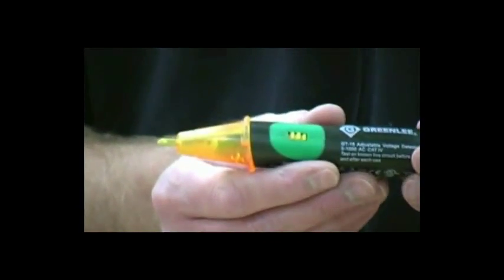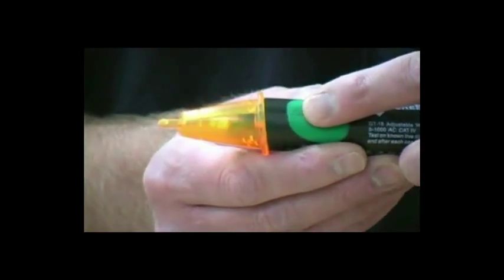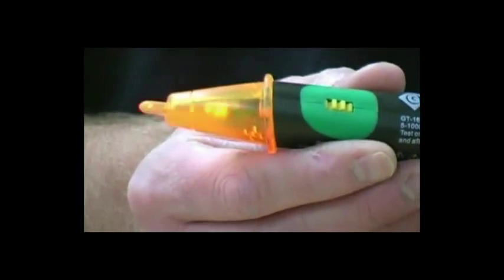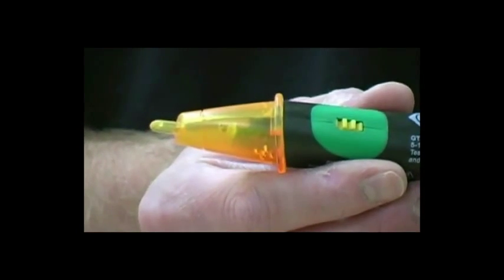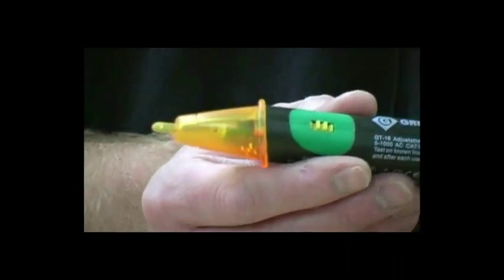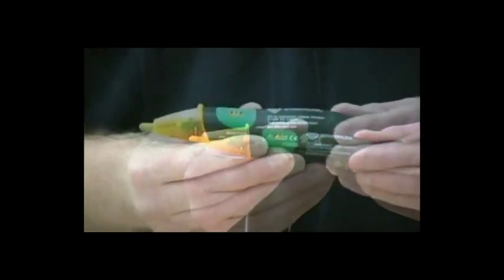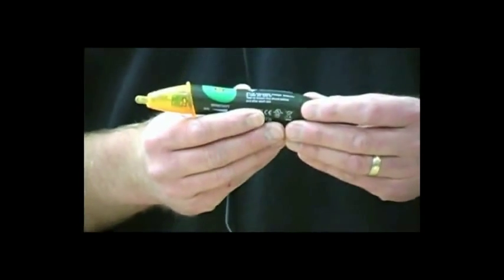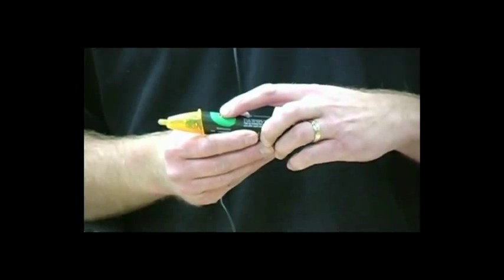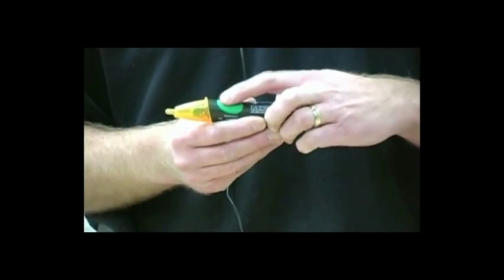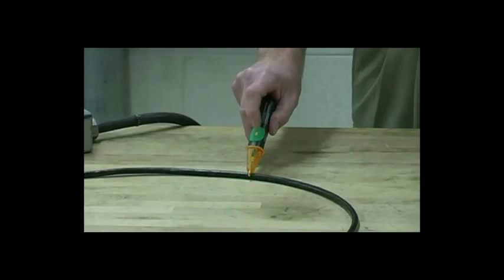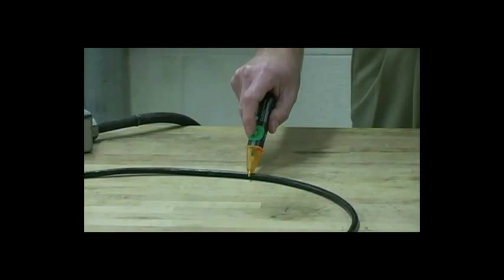To turn on the GT16, rotate the thumb wheel toward the tip. Verify the LED is blinking about every 2 seconds or so. This is a self-battery check feature. The GT16 combines the capabilities of the GT11 and the GT15 with an adjustable sensitivity dial. By rotating the adjustable sensitivity wheel towards the tip, we decrease the sensitivity. By rotating it back towards the cap, we increase the sensitivity.